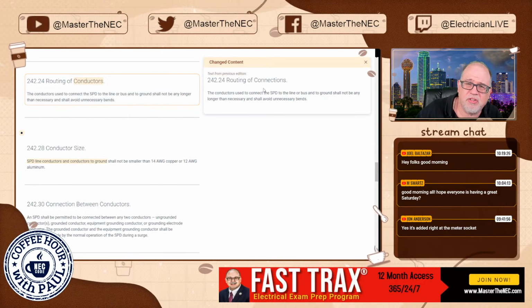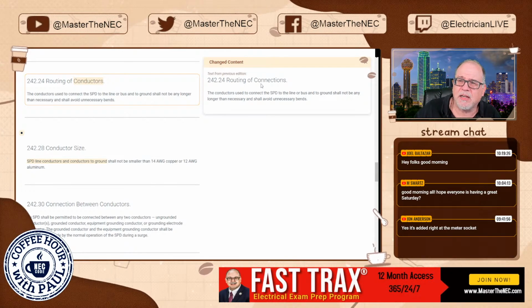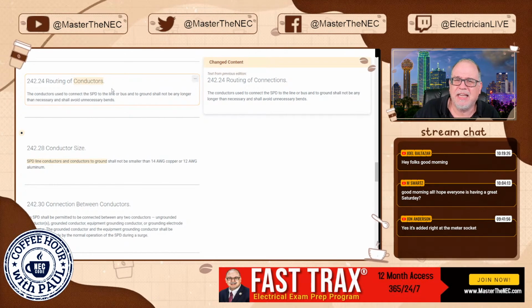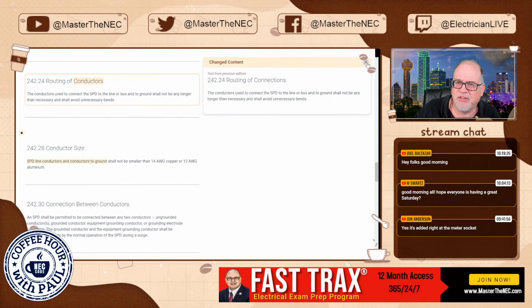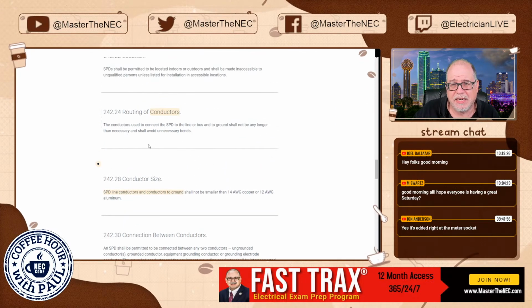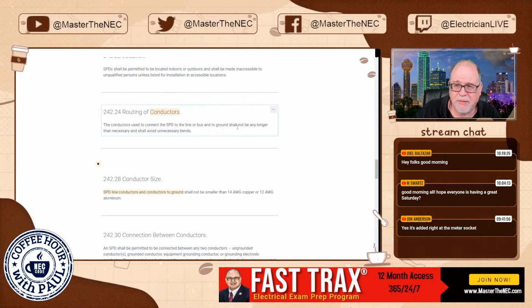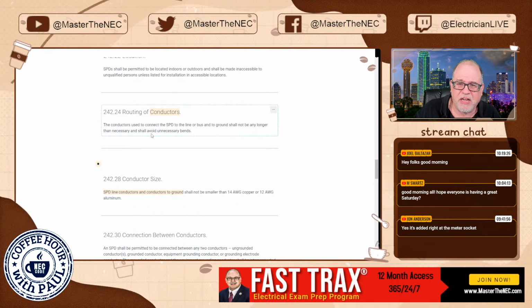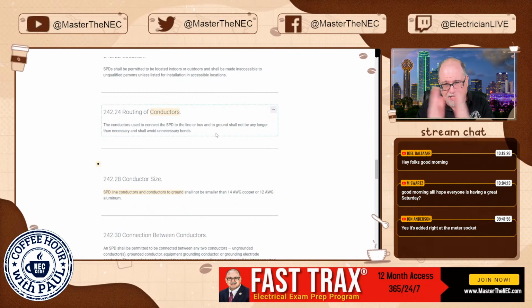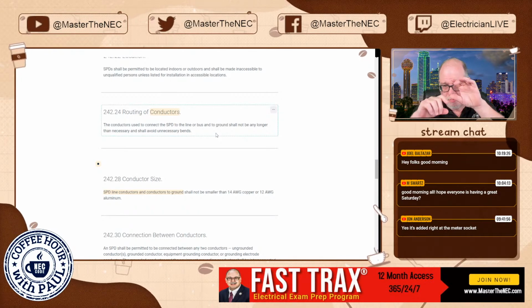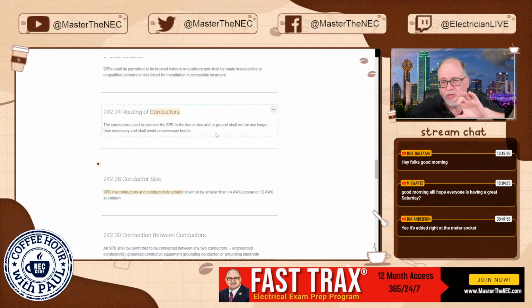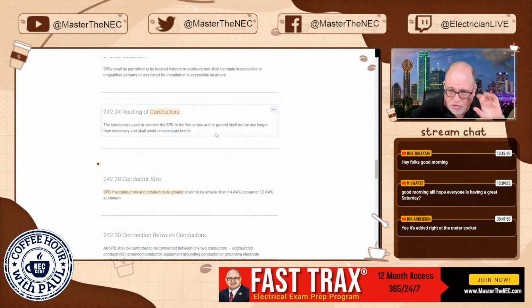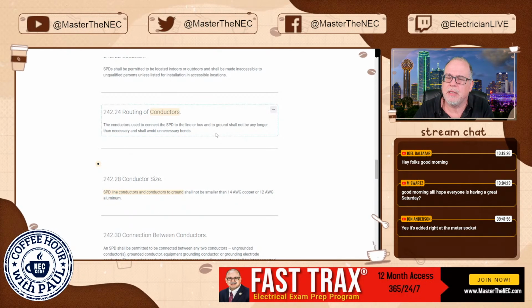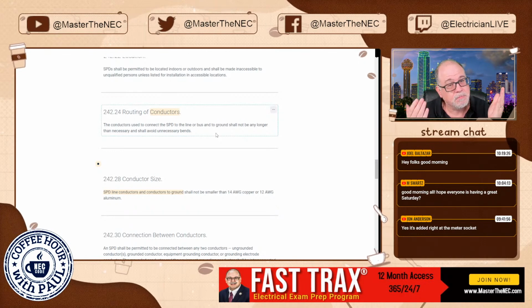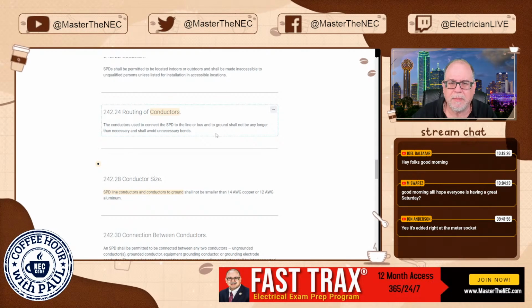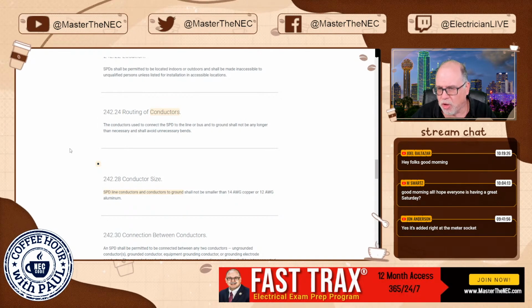So in the previous edition, that's the one on the right, it says routing of connections. Now, it was all about conductors, so it didn't change the intent here. It's just reminding you that they have to be no longer than necessary and shall avoid unnecessary bends. So try to keep them as straight as possible. Position them where you can in the panel so that if they are adjacent, you're bringing them in straight over to the overcurrent protected device. Make sense? Don't want to get all crazy and loopy up in there. Again, it could affect those devices.